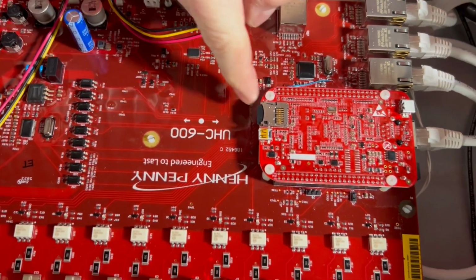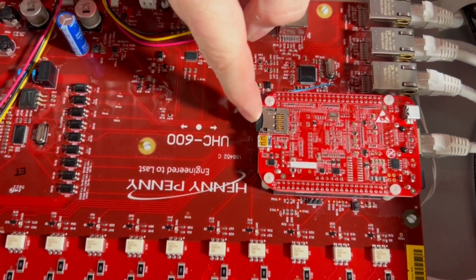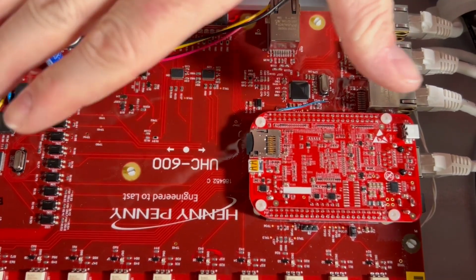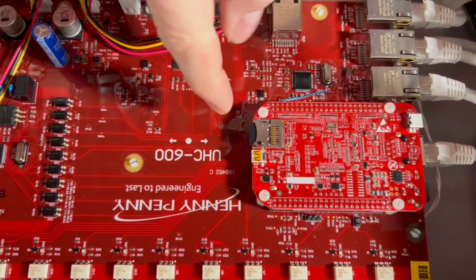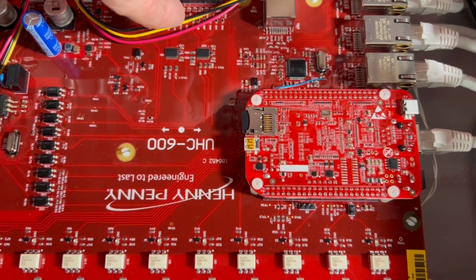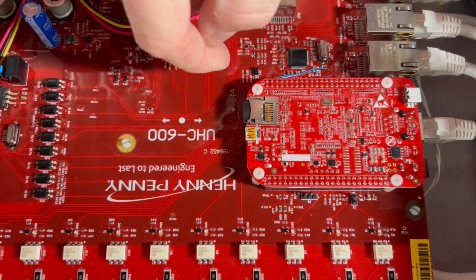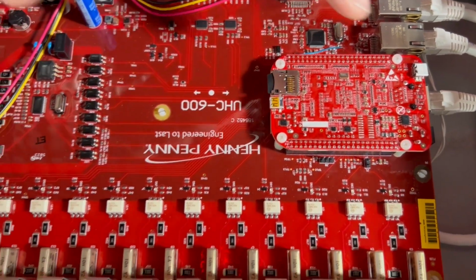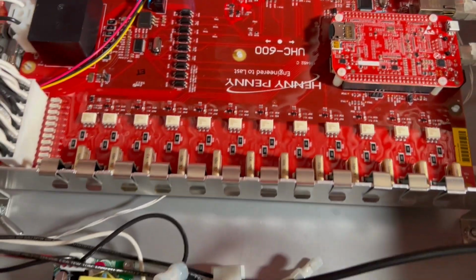If not, we want to try a new SD card before we go and replace the I/O board. However, if cleaning those contacts or replacing the SD card did not take care of the problem, then we're going to wind up needing a new I/O board.